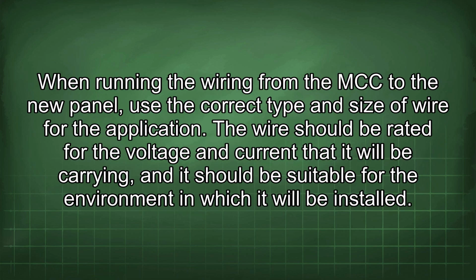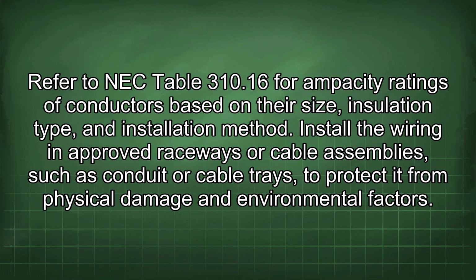When running the wiring from the MCC to the new panel, use the correct type and size of wire for the application. The wire should be rated for the voltage and current that it will be carrying, and it should be suitable for the environment in which it will be installed. Refer to NEC Table 310.16 for ampacity ratings of conductors based on their size, insulation type, and installation method.